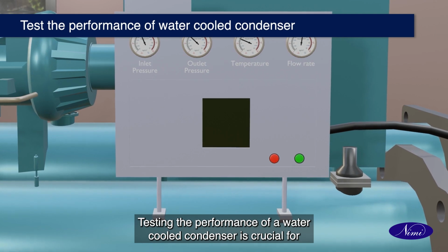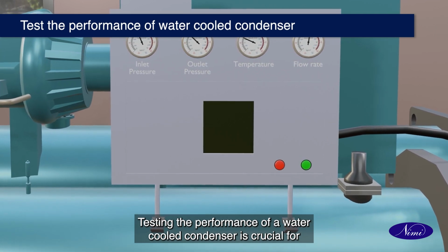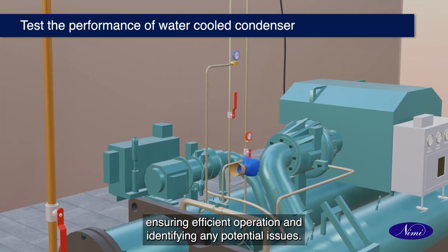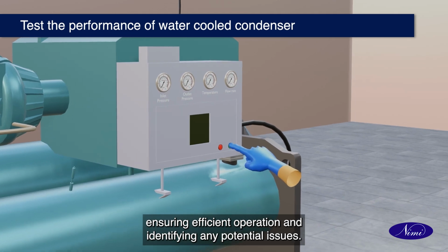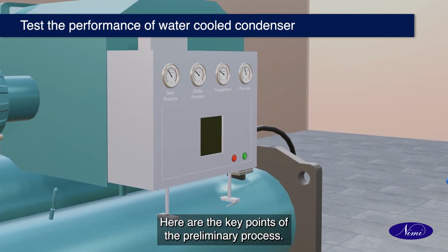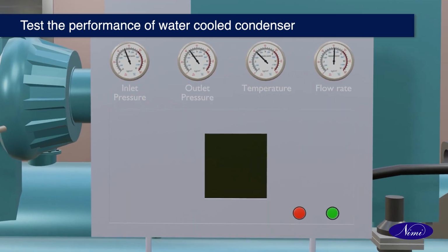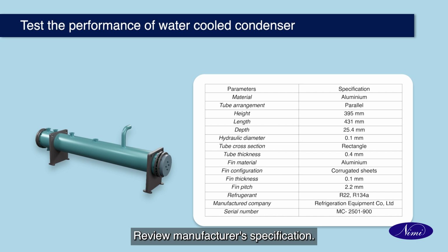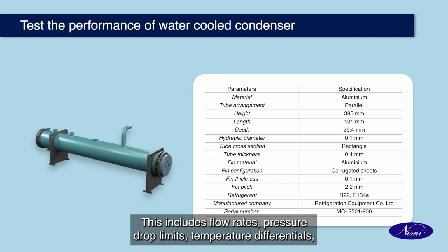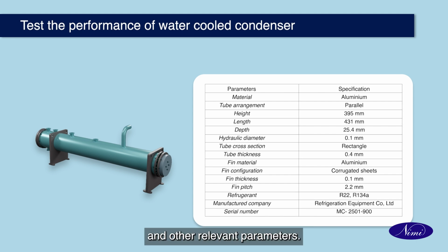Testing the performance of a water-cooled condenser is crucial for ensuring efficient operation and identifying any potential issues. Here are the key points of the preliminary process. Review manufacturer specification. Understand the design and operational specification provided by the condenser manufacturer. This includes flow rates, pressure drop limits, temperature differentials, and other relevant parameters.